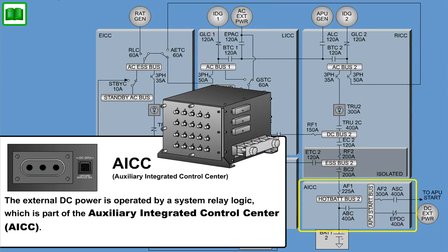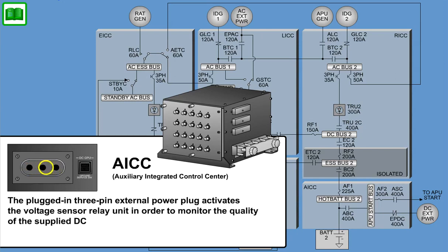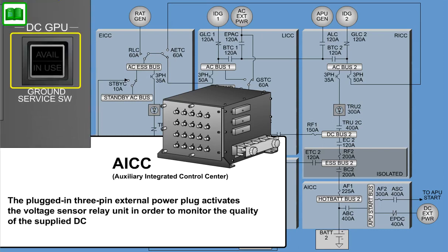AICC. The plugged-in 3-pin external power plug activates the voltage sensor relay unit in order to monitor the quality of the supplied DC. The DC GPU ground service switch on the DC GPU power panel is the manual control and will indicate avail when acceptable external DC quality exists. Pressing the switch will cause an in-use indication to illuminate.